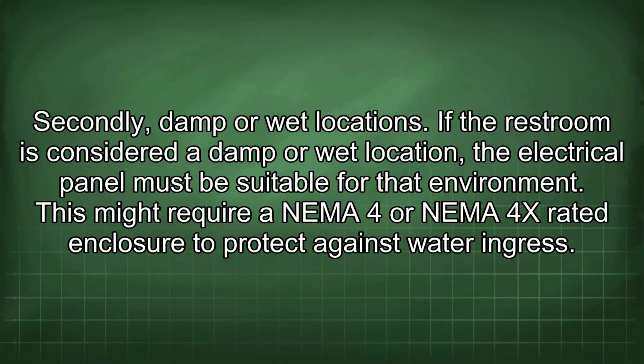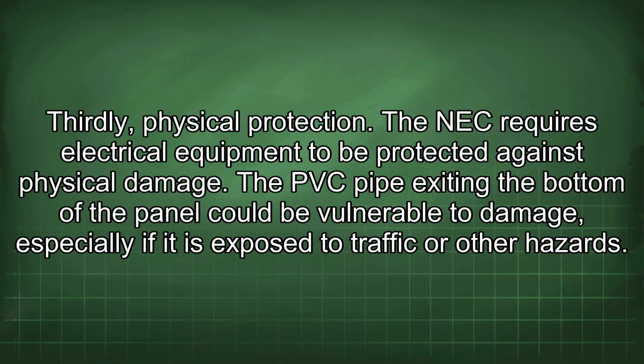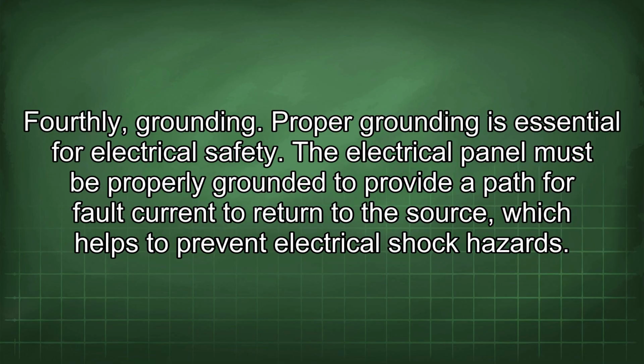Secondly, damp or wet locations. If the restroom is considered a damp or wet location, the electrical panel must be suitable for that environment. This might require a NEMA 4 or NEMA 4X rated enclosure to protect against water ingress. Thirdly, physical protection. The NEC requires electrical equipment to be protected against physical damage. The PVC pipe exiting the bottom of the panel could be vulnerable to damage, especially if it is exposed to traffic or other hazards. Fourthly, grounding.